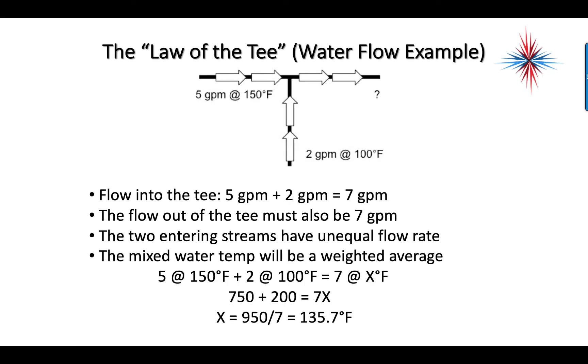Now what happens when we have two different rates? We still have the law of the tee, which means what comes in must go out. So I have five gallons per minute at 150 degrees and two gallons per minute at 100 degrees. We know our inflows are five and two, so our outflow must be seven. Now the two entering streams have an unequal flow rate, so the mixed water temperature will be a weighted average. We have five at 150 plus two at 100 equals seven total at X degrees.